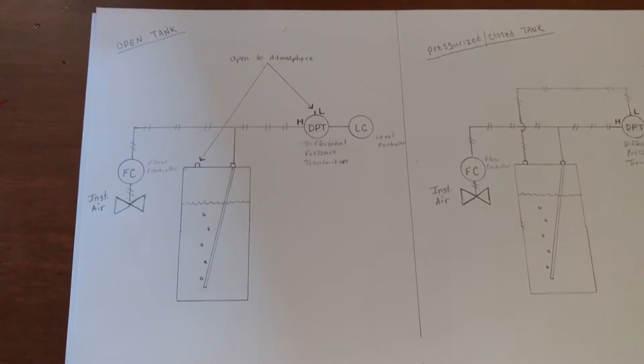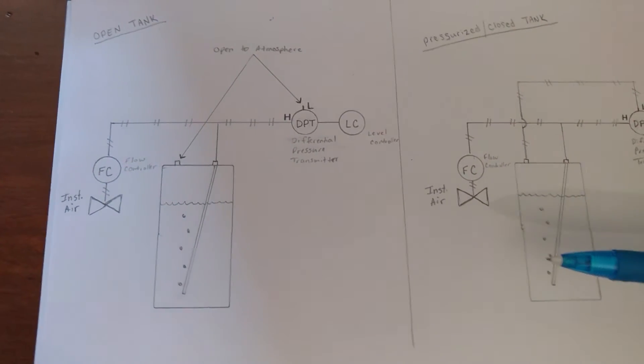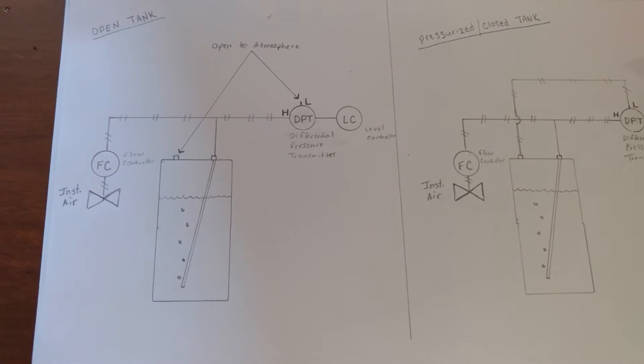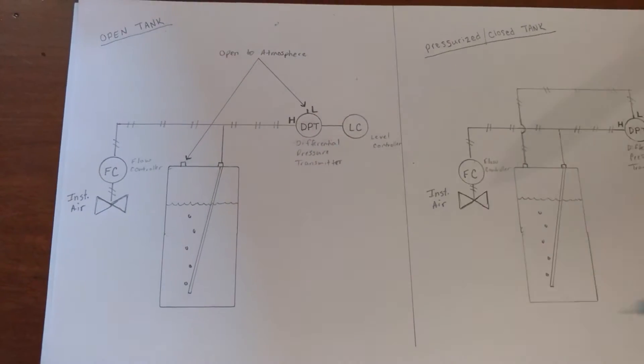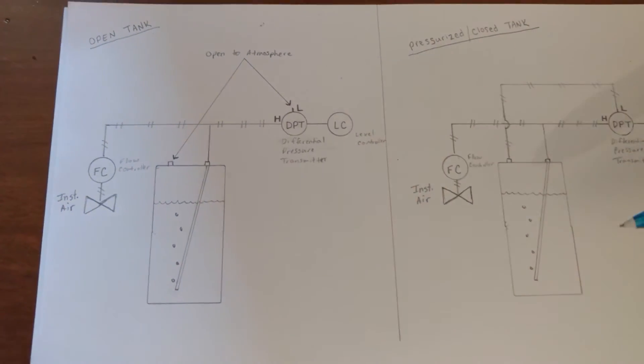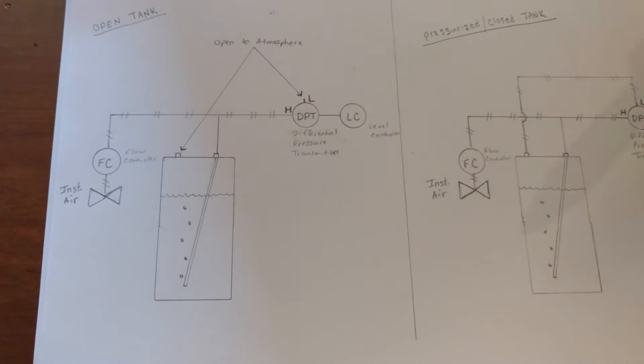So a bubbler system is a system that you're going to use to find the level of a tank, a pressurized tank, a vessel with liquid in it, or a pond, where you don't have access to the bottom of the container and you can't use a hydrostatic pressure transmitter.